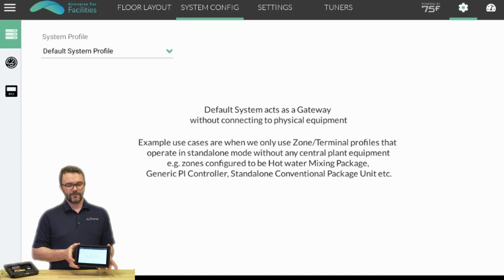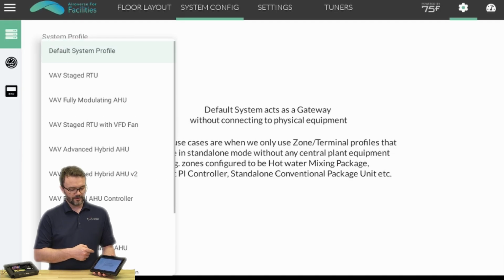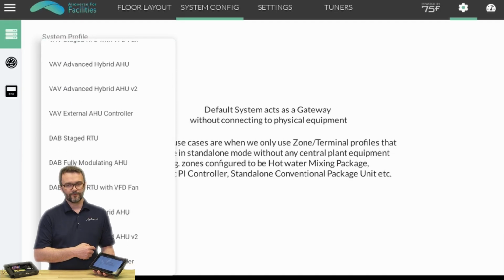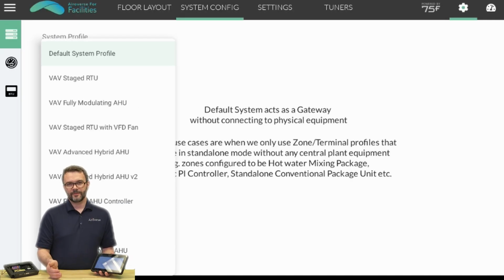But if this is going to be used as a zoned air handling unit control, we need to select the type of control we want it to follow. There are two primary types: VAV, variable air volume, which uses some iteration of ASHRAE Guideline 36 and the associated trim and response mechanism from all the zones to control the AHU.